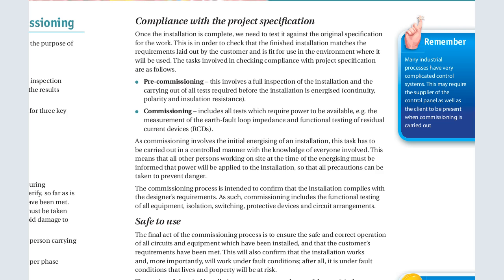Now, commissioning itself includes all tests which require power to be available, e.g., the measurement of the earth fault loop impedance and the functional test of the residual devices. The RCDs are protective devices that are normally used for power that is temporarily installed, for example, on working areas that are very risky, like an installation site or a construction site, or maybe somebody working outside the building, maybe a grass cutter. Those devices or appliances are normally protected using the RCDs. The RCDs are also called the residual current devices.